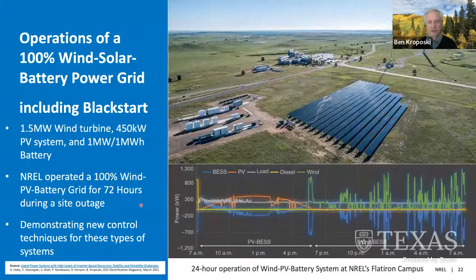So we've been able to demonstrate this at our own location here in Colorado, where we've operated a 100% wind solar battery powered grid. You can see the megawatt scale wind turbines, about 0.5 megawatt of solar panels, and then megawatt scale batteries, and we were able to operate the building loads at this location. We actually operated it for 72 hours, completely on this 100% wind PV battery grid, and we were able to demonstrate black start capabilities from these devices. We devised some advanced control techniques to allow this that we think could be deployed across much larger scale systems. You can see a graph down here on the bottom of the solar coming up, this orange line, so that's producing sunlight. The gray line here is the load, and then the blue is the battery either being charged or discharged to maintain that load level. And then at nighttime, the wind is coming on and producing energy to provide energy to the loads.